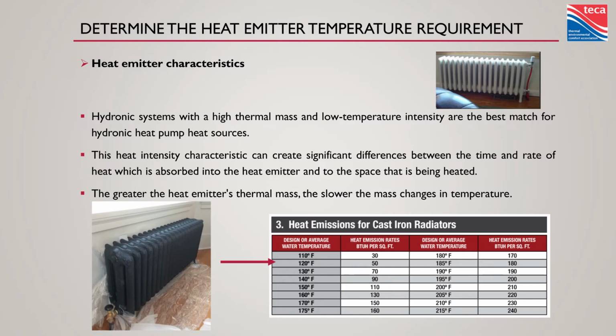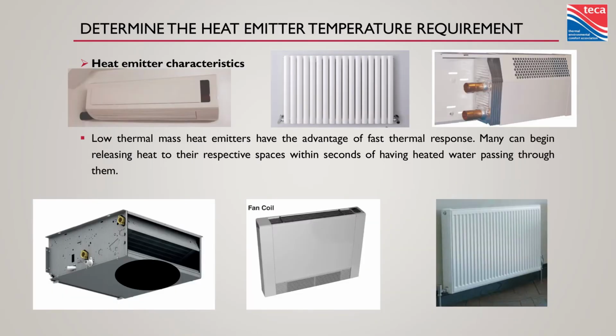They work great. On top of that, we've got some fan coils on the market. You might say, hey, that looks like a ductless mini split. It kind of does, but it's hot or cold water running through it. So this would be a great way to retrofit some cooling into an existing radiant floor system. Toss something like that up in the primary bedroom, and now you've got some summer cooling out of that heat pump that otherwise was just sitting there until it became heating season again.